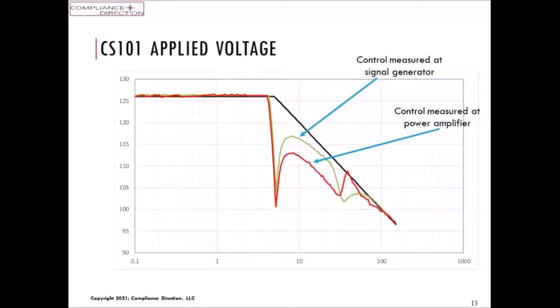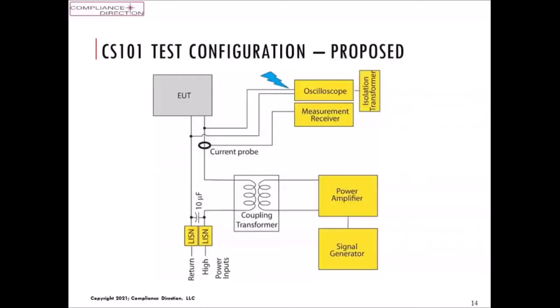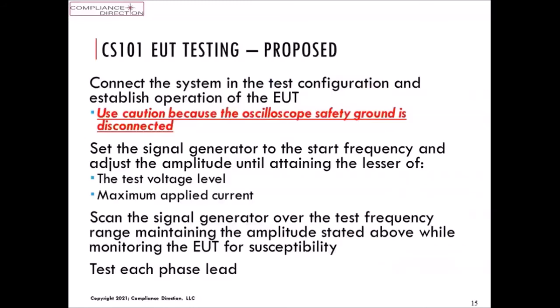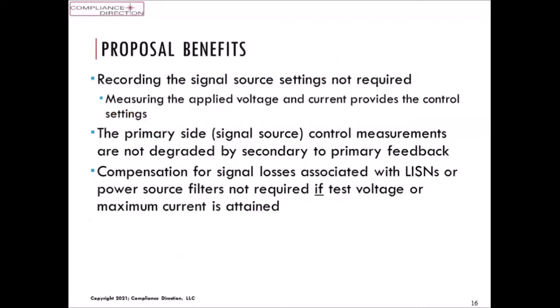Excuse me, I went the wrong way here. So the proposed method connects the system. Remember again, the oscilloscope's still got that safety disconnect, and we set the generator attaining the lesser of the applied current or the test voltage. And we scan the generator over range, maintaining that with the test in each phase lead, just like we would normally do, except now we have the current feedback to be a control point.